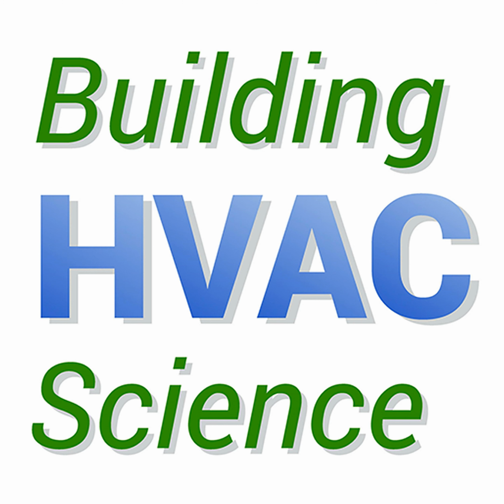But with the ability to load match on the glycol side, you're not really going to run that. Just because a compressor's running doesn't mean you've got to have 1.5 tons of cooling on the water side, correct? That's right. Yeah. So you can modulate the water side down even lower than 1.5 tons. Yeah, it can match exactly what the indoor requirement is. On the amperage side, we also have a tech called dynamic load balancing. So if someone has a limited power capacity, we can match their maximum. We can run the system so that we are not consuming more than their allowed capacity.